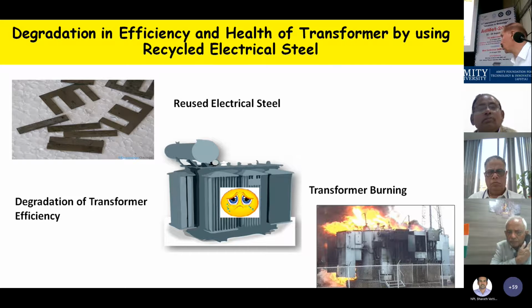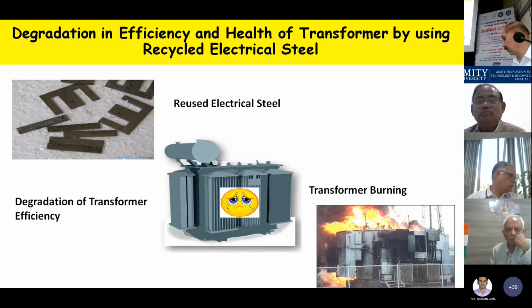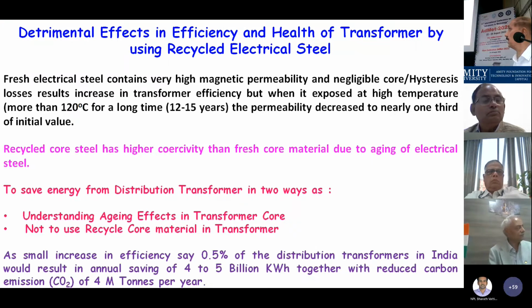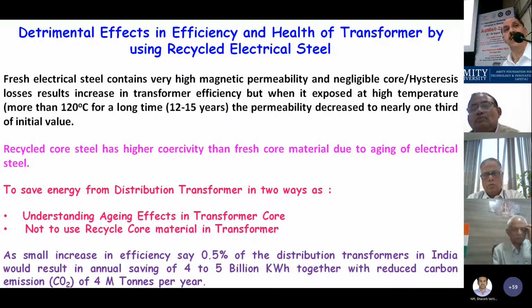Same is the situation for the transformer core, because transformers are burning because of the quality of the core, on which the winding is done. So that is to be taken care of, and that work was also done. I'll not get into the detail of this, but I'll talk about the detrimental effects on efficiency and health of transformers from using recycled electrical steel. I also worked on this with the Power Ministry way back in 2014, on how we can stop this recycled electrical steel, which was being used in transformers and then sold in India, by increasing the customs duty on it.